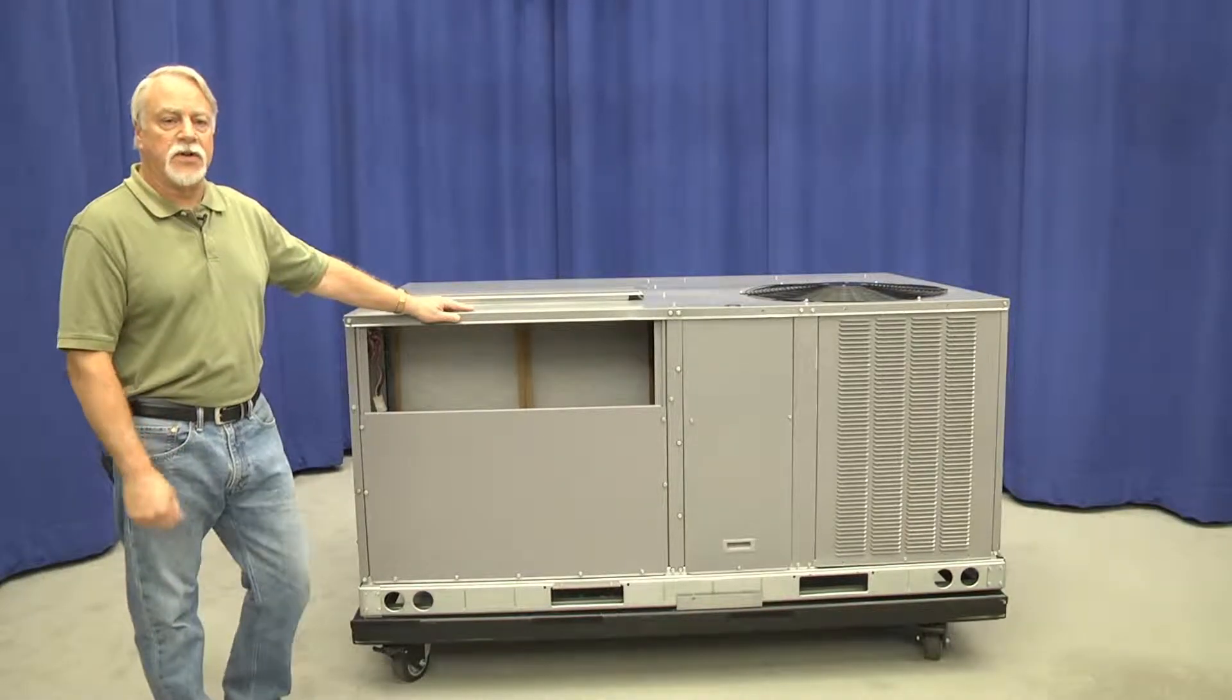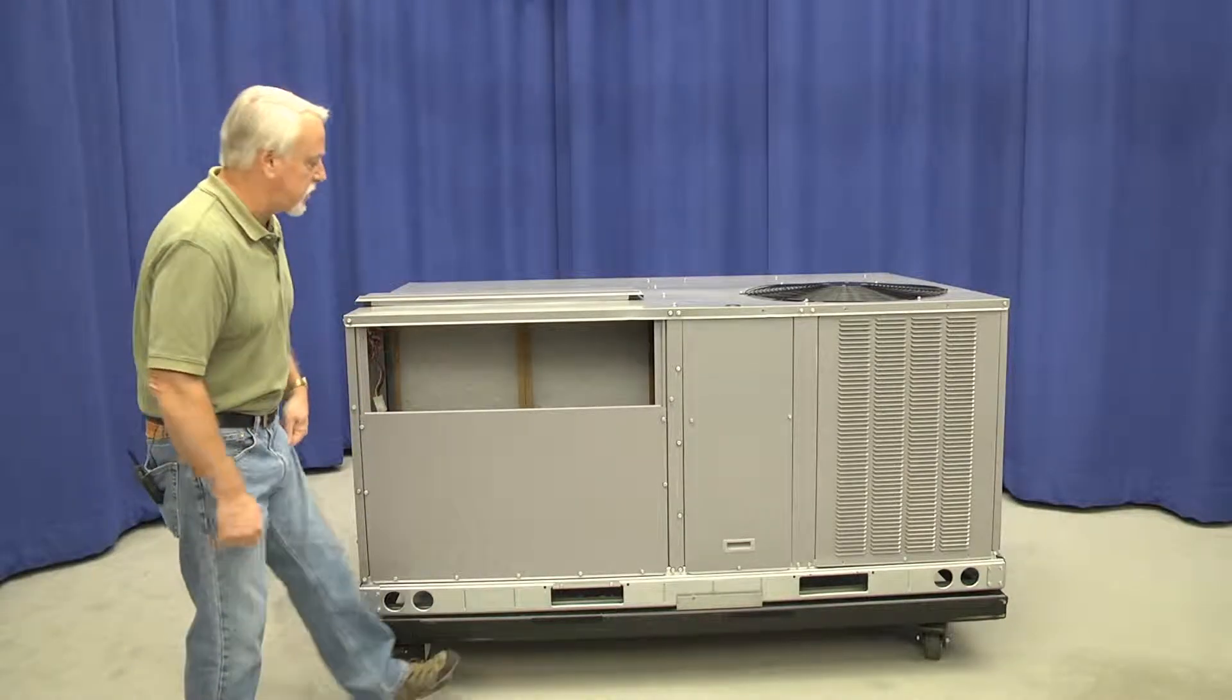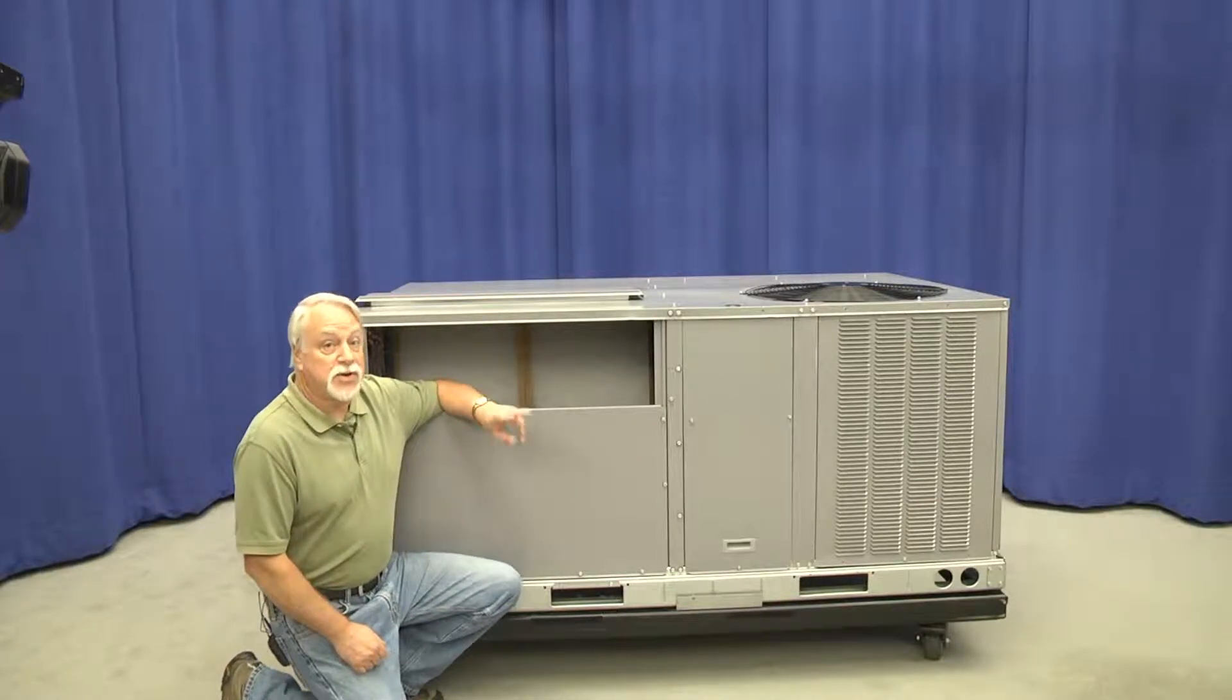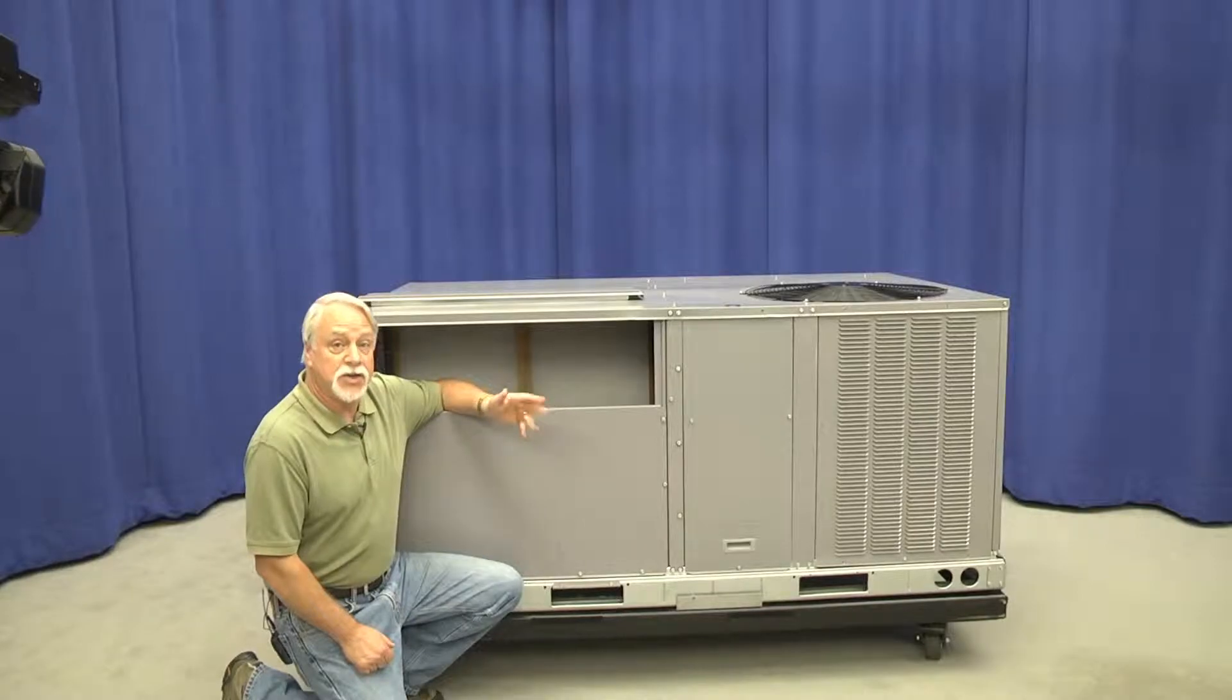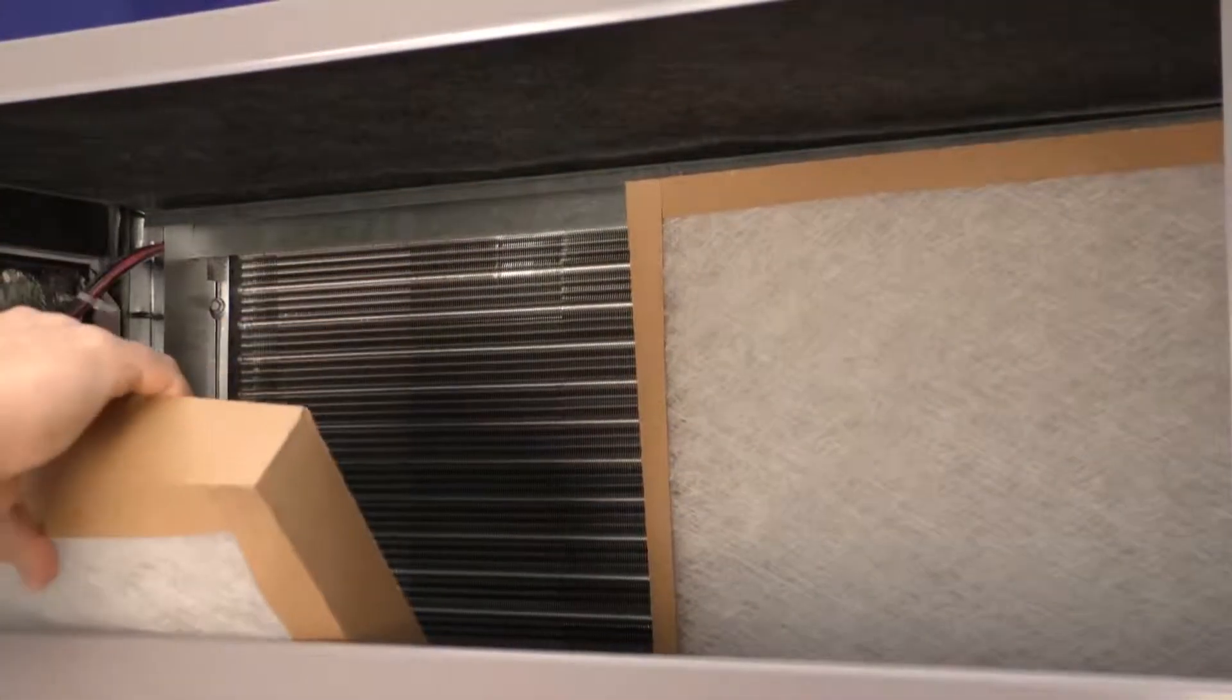The standard filters for this machine are the 2-inch, 10% efficient throwaway filters. Accessing those, there's still two in this particular chassis size. We still have that hinged rail at the top of the filter rack that allows these filters to be pivoted forward and removed from the unit for easy service.